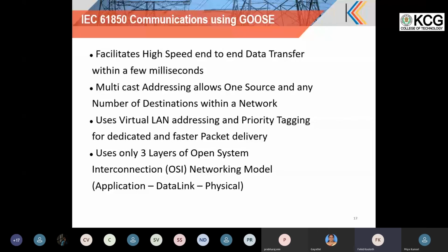Instead it has a publisher-subscriber mode. So every node in the system can subscribe to a GOOSE, and when a publisher, that is the one originating the GOOSE, publishes it, those subscribers will get the GOOSE. It is similar to a book getting published to its subscribers. A similar scenario is adopted in GOOSE: one source, and you can have multiple destinations in a network.